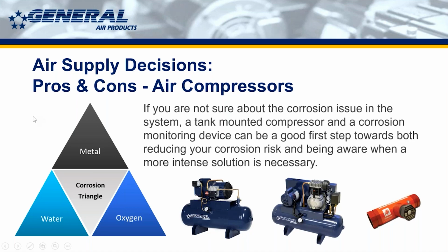But one of the ways that I do recommend setting up a compressor for corrosion mitigation purposes is by using a product that I'm sure George will be talking about, which is their corrosion monitoring device. They call it their Core Insight. I really like the way that it's designed to operate mechanically. This is a really good way to approach corrosion if you're not sure that you have a corrosion problem, or if you're concerned about having one but don't want to make the investment, which can often be very significant cost-wise in a nitrogen generator or a dry air generator.